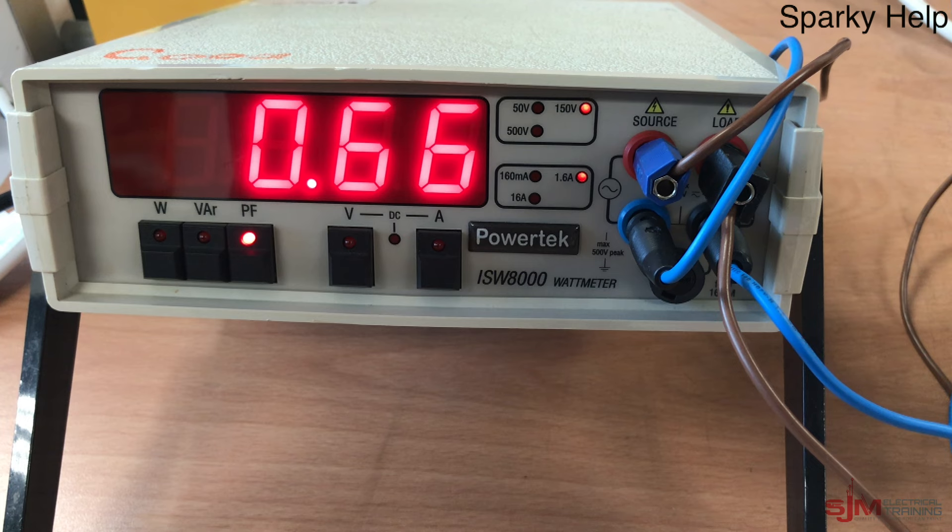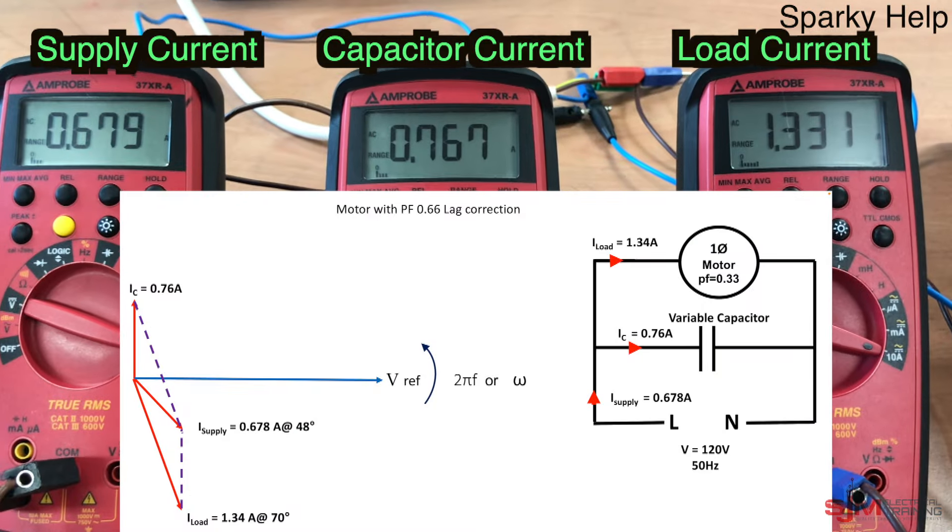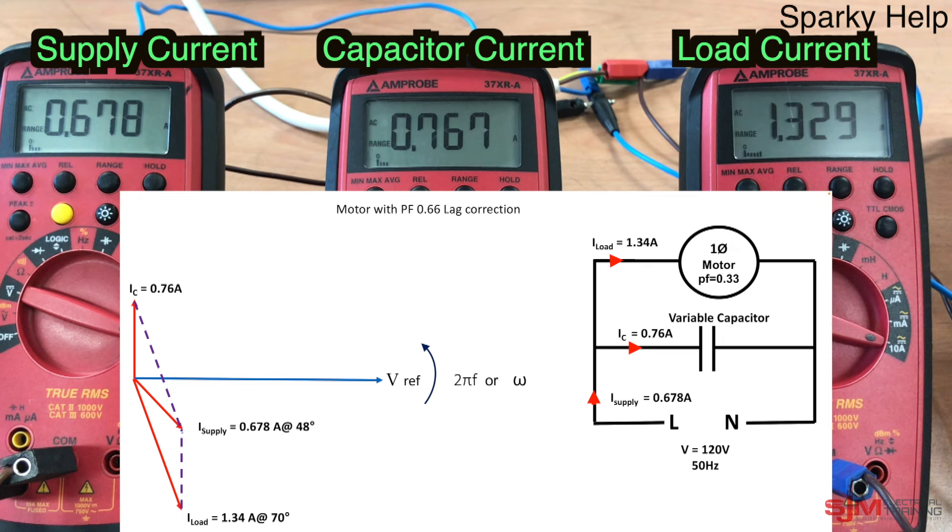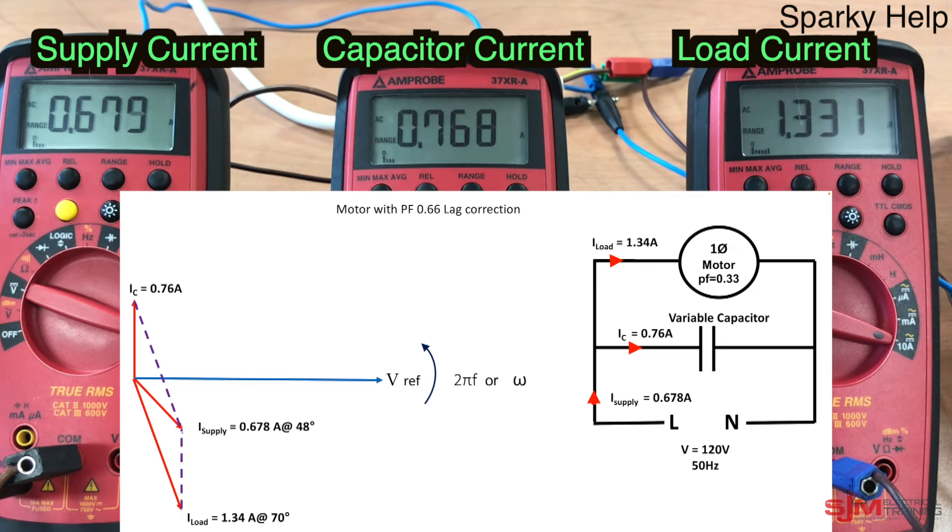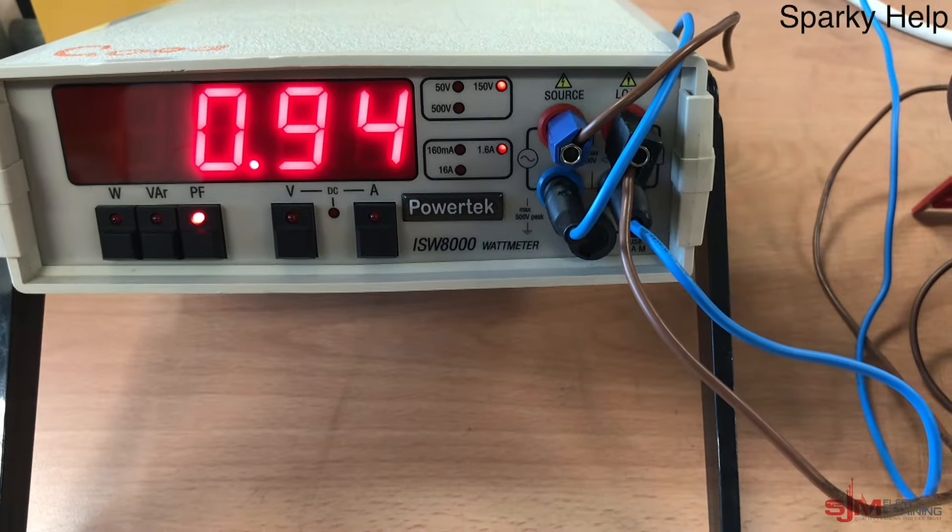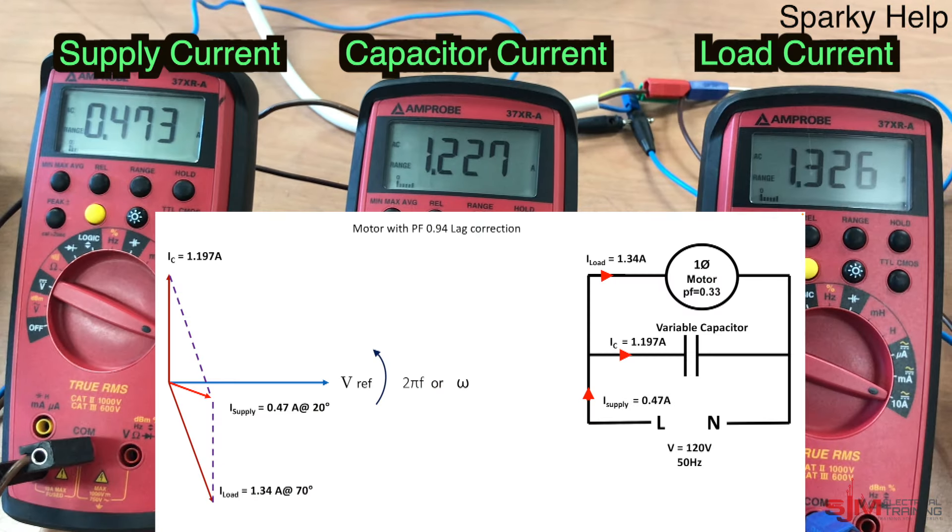Let's add in some capacitance. As we can see the power factor has improved to 0.66. Let's have a look and see what it does to the currents. And the phasor diagram. So the phasor diagram has moved up. The supply current has gone down. And we have current going through the capacitor. And the supply to the load is still the same. And the power is still the same.